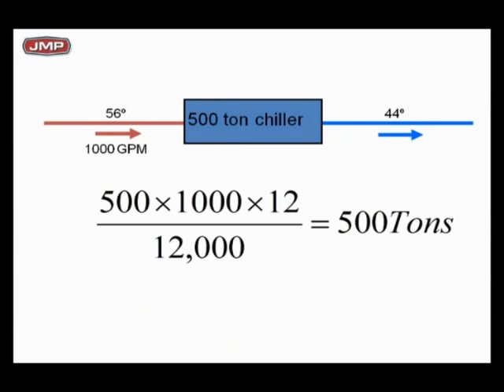And as you can see with the BTU formula, 12,000 BTUs per ton, that is a 500-ton chiller. I want everybody listening to me, just sometimes I sound a little crazy when I say things, but get this in your head. This is worth you listening to. You cannot load anybody's chiller up unless you get the return chill water temperature up. If you don't give a chiller the designed return water temperature, you can't get the tonnage out of it.